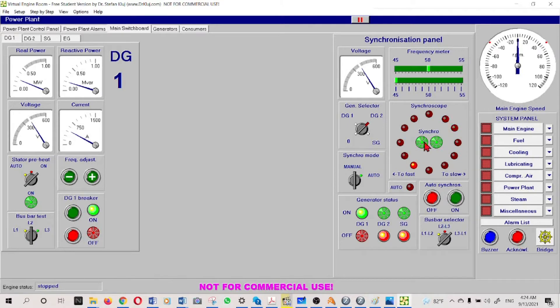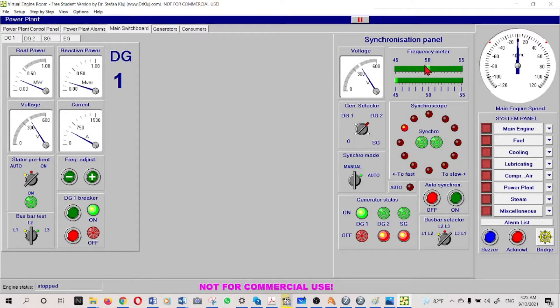The switches here - we can see the synchroscope and the frequency meter. Normally the synchroscope must be switched off; we will only switch it on when we are going to synchronize, but here we let it be. The frequency meter shows the bus bar frequency - we can see it is at 50Hz. The system is designed to run on 50Hz. The simulator is designed that way. Here is the bus bar voltage.